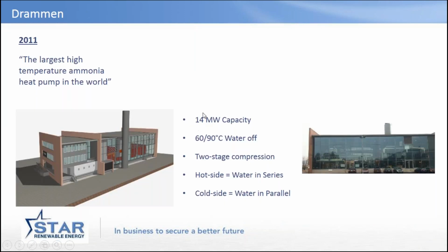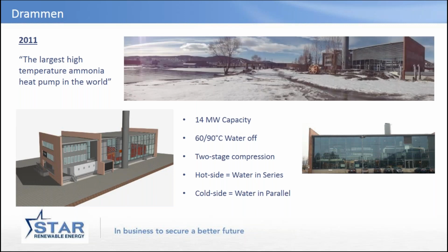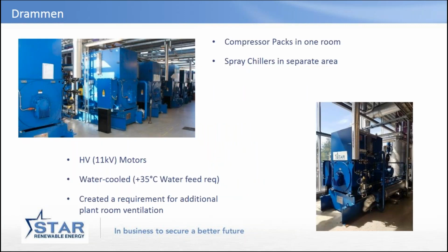What we did in Norway, because it's a much larger system using ammonia as a working fluid, we're getting much, much higher efficiencies. Heat pumps are very honest devices. They take in electricity and they give you heat, and the operators really just want the maximum ratio. So pretty chunky, as you can see from this. Quite hard to get a good photo because it's hard to stand far enough back. We were so focused on the efficiency, we even harvest the waste heat from the electric motors, which is typically around about 3 to 4%. So definitely not to be sniffed at.